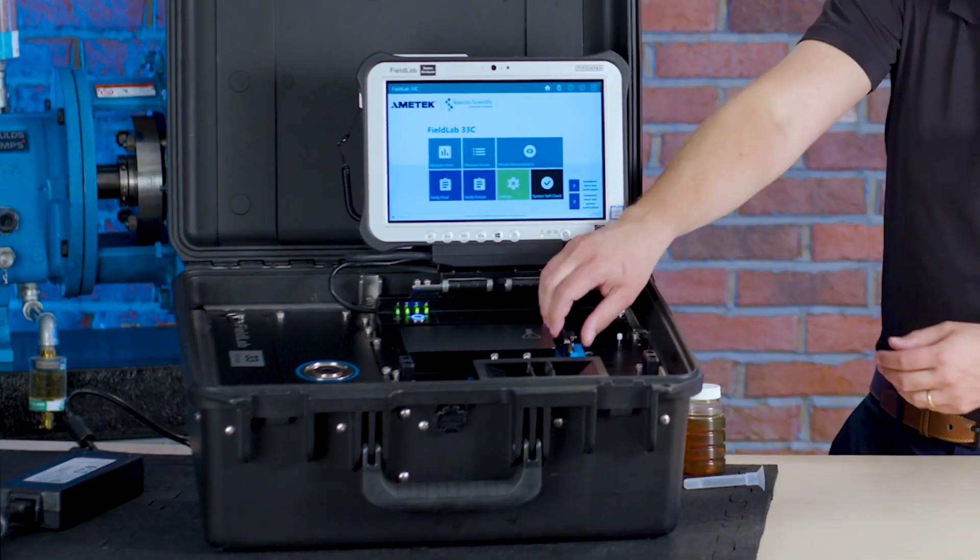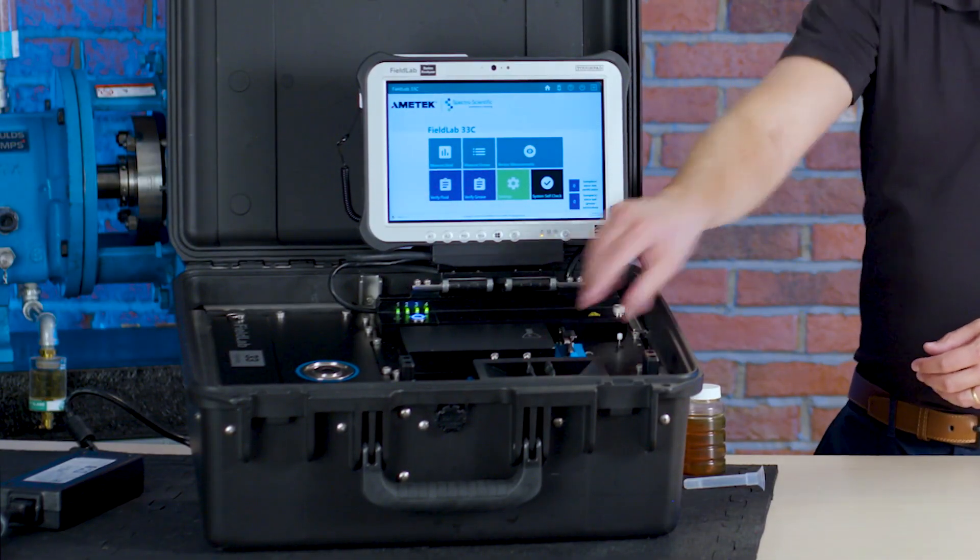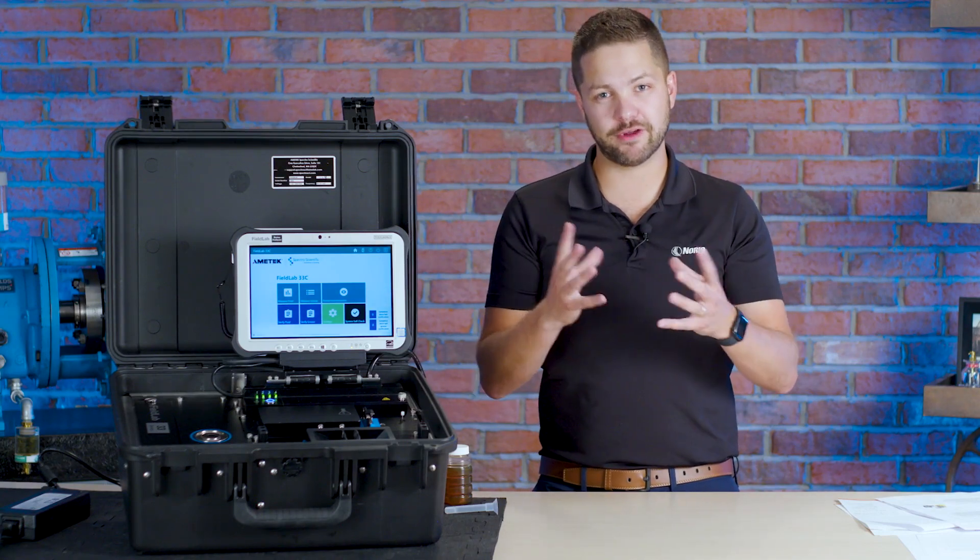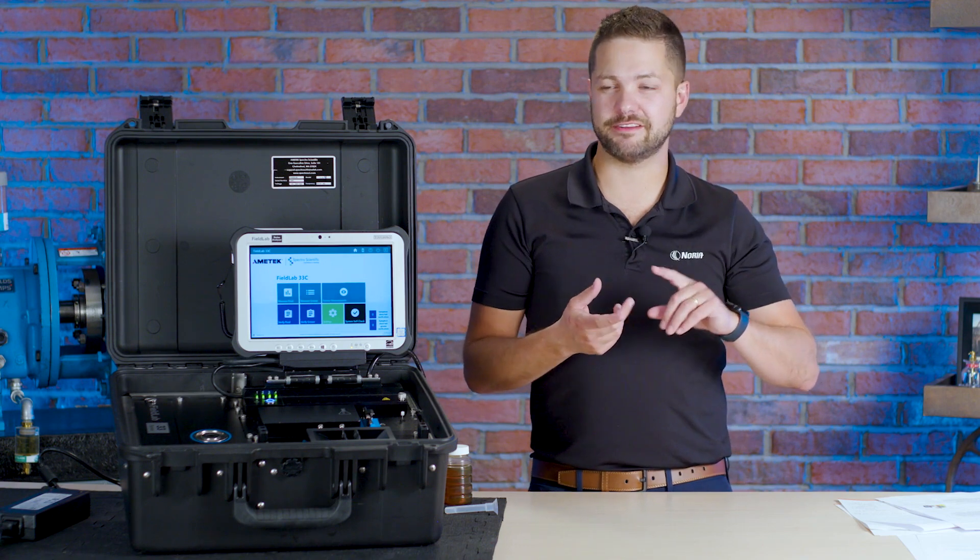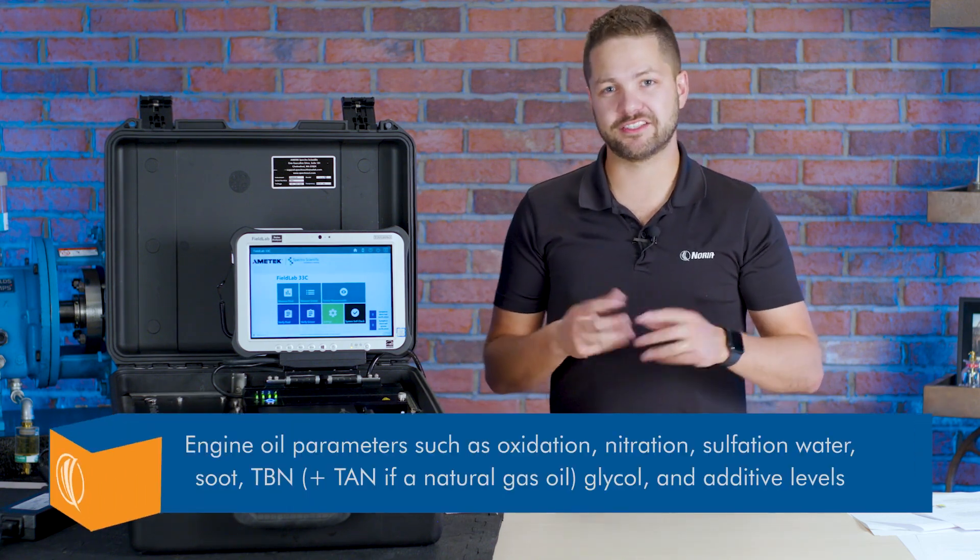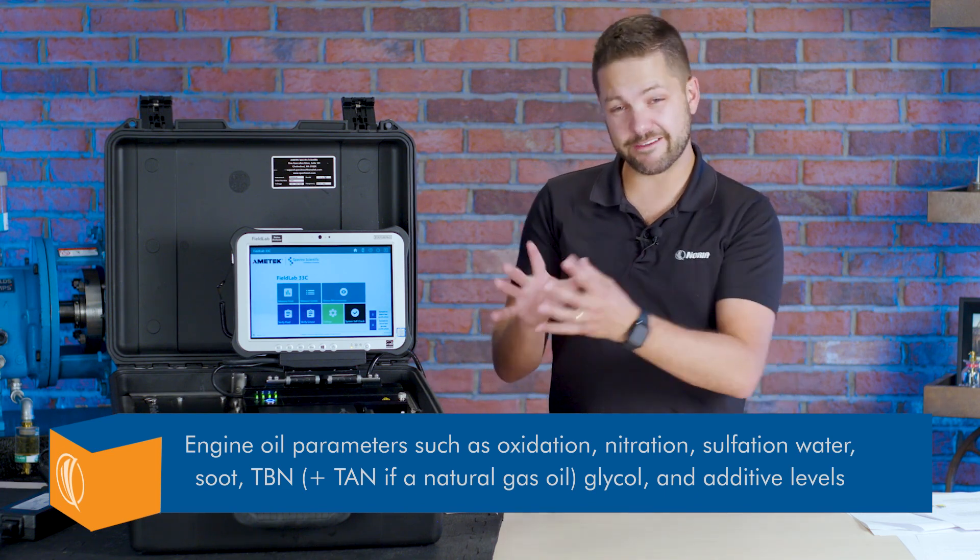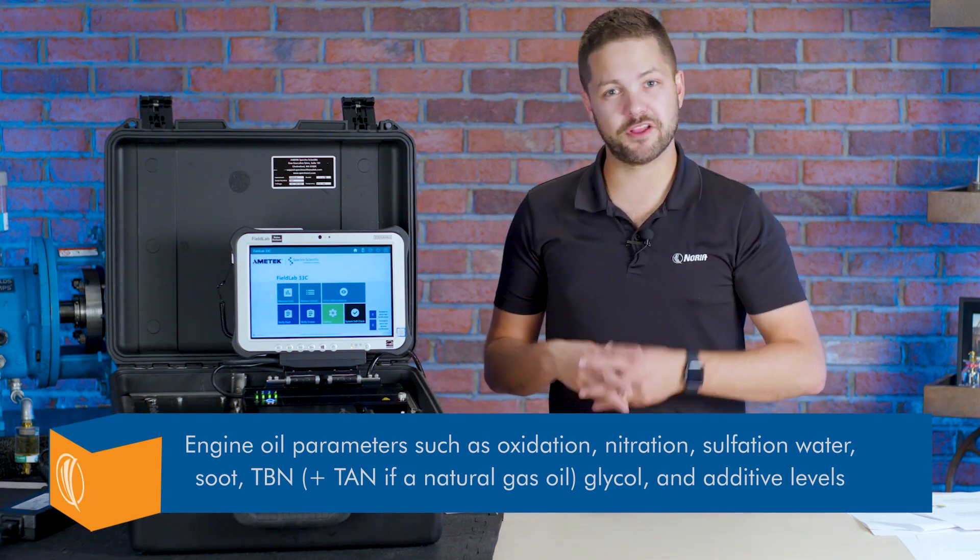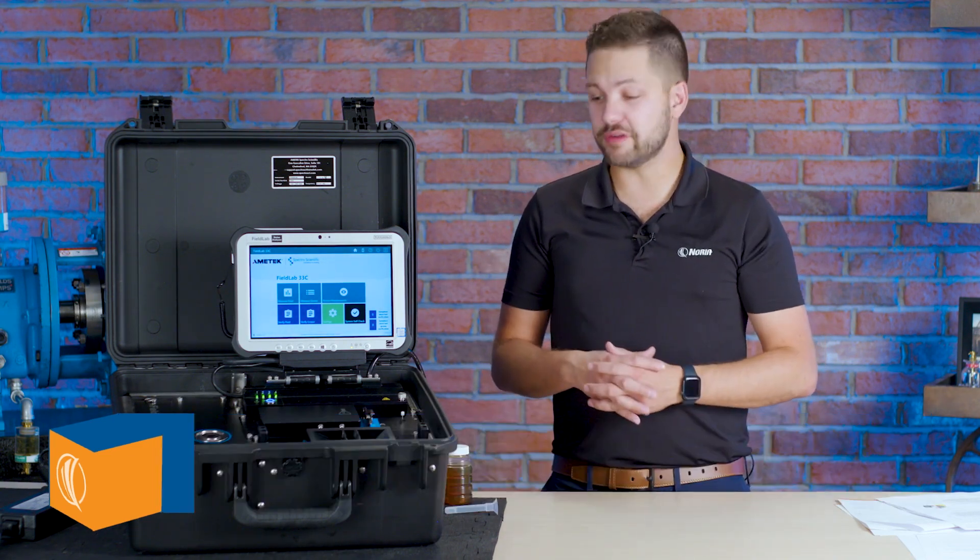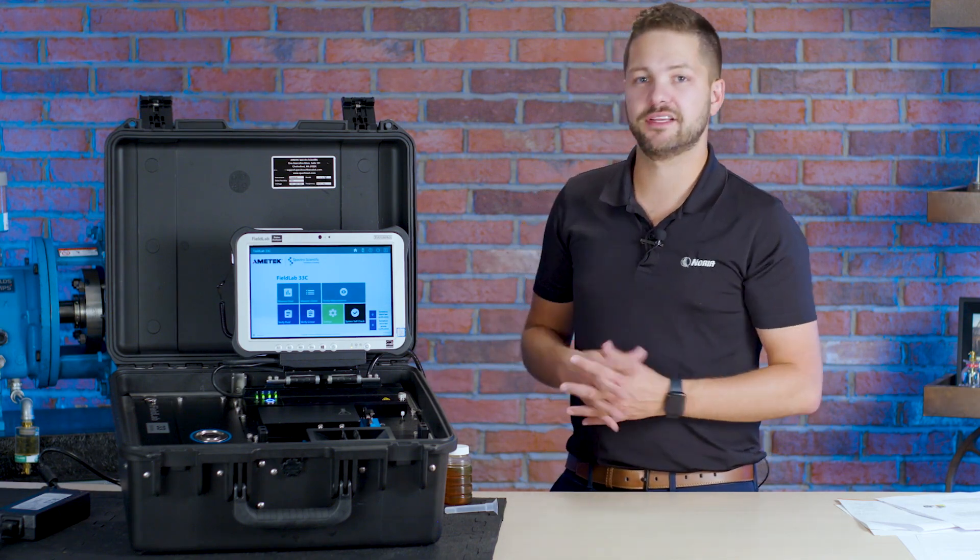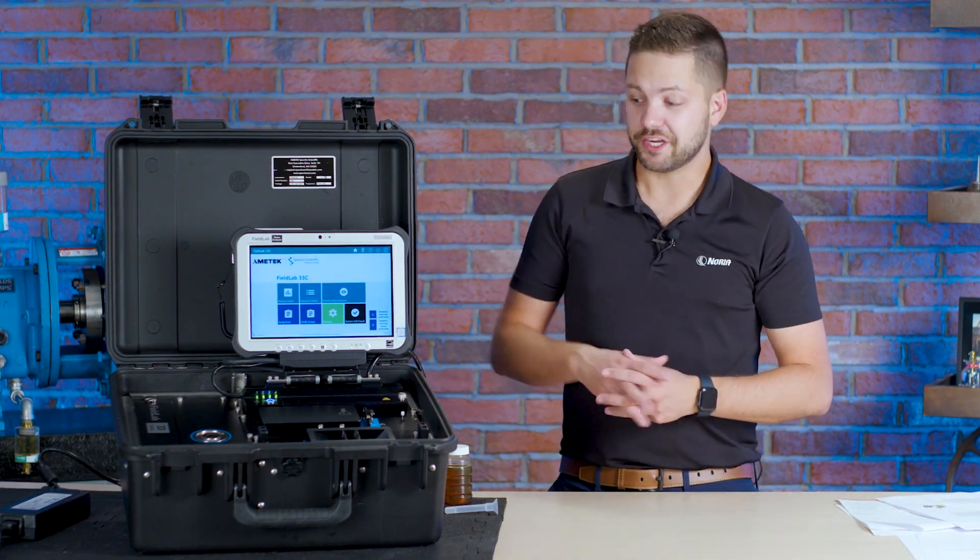The next one here is the fluid scan technology which is looking at the different molecules of the oil through an infrared technology here. This is different things like if it's an engine oil you might be looking at soot levels, glycol levels or the fuel content if it's gotten into the engine oil. For other machines you'd be looking at oxidation levels, nitration levels, water content, you name it. There's several parameters all molecular based that you can analyze with this technology right here.